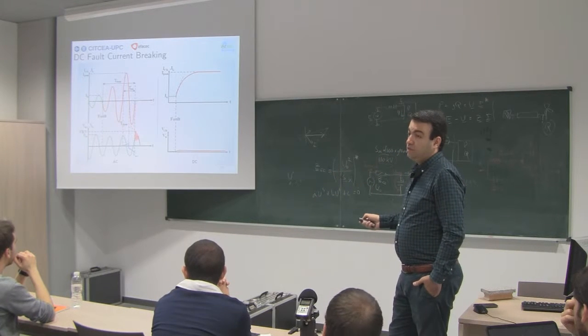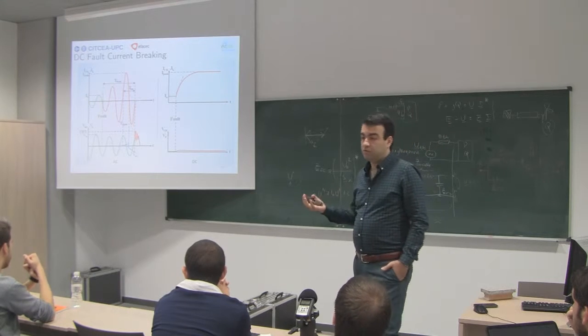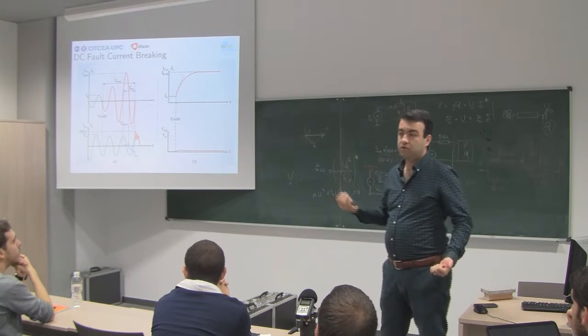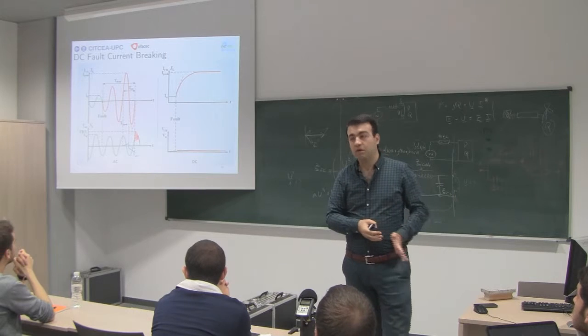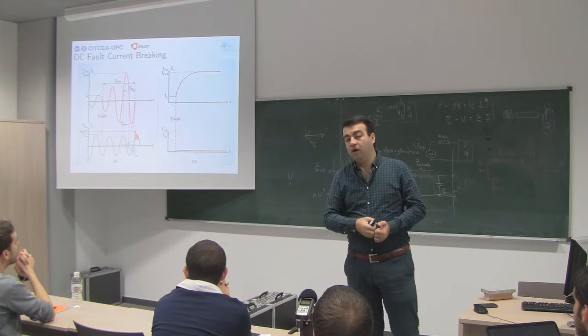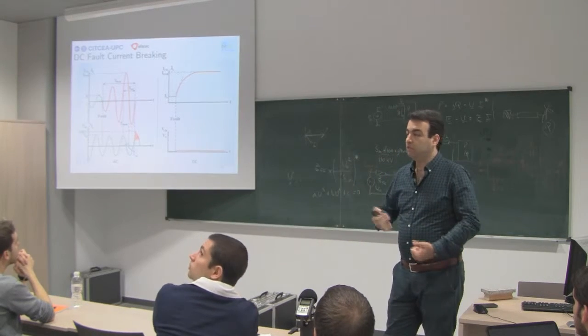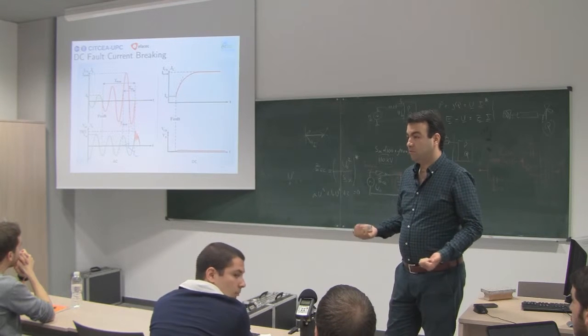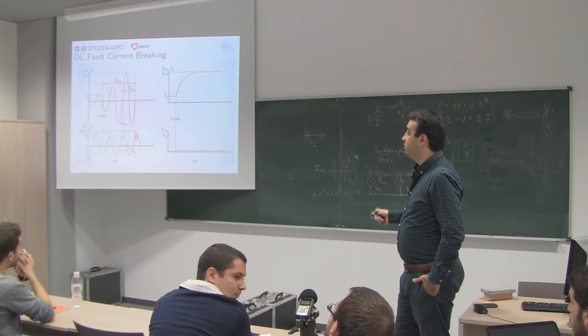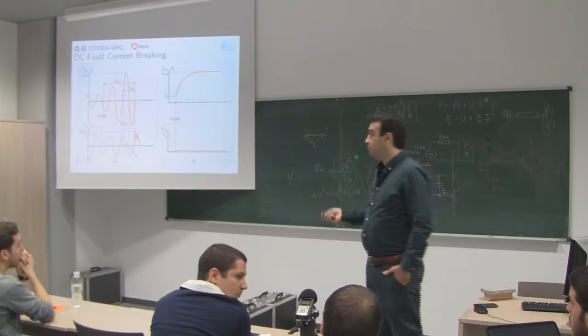But it's not like this in DC. In DC, we don't have a zero crossing point. So if we open a circuit breaker with the same technology as in AC, the arc will be drawn, but it is not possible to interrupt it. You will have a permanent current even if you open the circuit breaker.